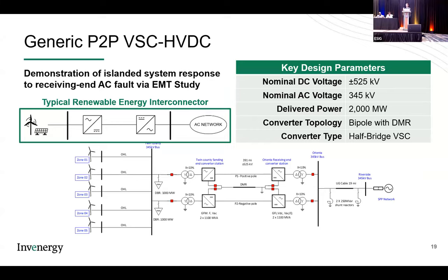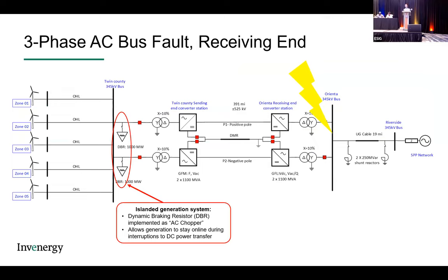And so this isn't Grain Belt specific. We're looking at a typical 525 kV bipole with DMR, 2000 megawatt, and the topology is at the bottom there. So in this islanded system there's a dynamic braking resistor that is typically added. It's a little different in offshore because you have all the constraints of an offshore platform, but onshore you look at that on the AC bus with the generation, and it's used to dissipate the renewable generation on that side during a system fault on the DC side or the AC receiving end, where you have an interruption of power transfer capability. It keeps you from having to cross trip all the generation in any sort of disturbance like that.